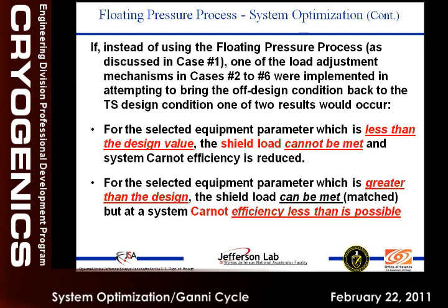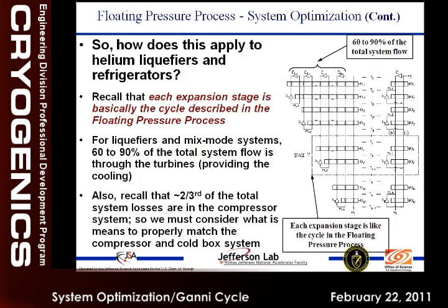By taking away the controls, basically what we do in floating pressure is we move the controls to protection of the devices, not as controls for the process. We allow them to move the entire range where they are not destroying themselves. So that way they can float up in pressure and temperature or float down and still cover the range. So if the components become more efficient than we think, we can meet our design capacity at a higher thermal efficiency than originally designed. And if we restrict it, we cannot meet the capacity. That's basically what happens if we follow the fixed.